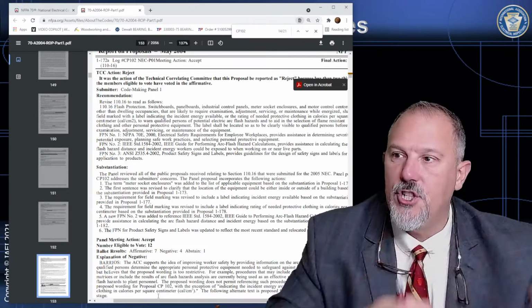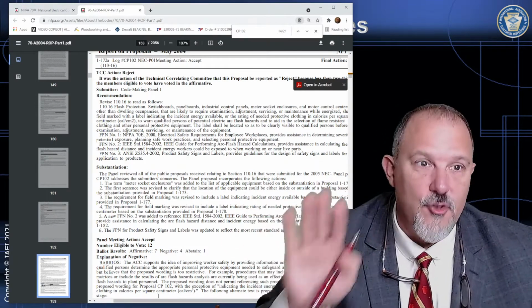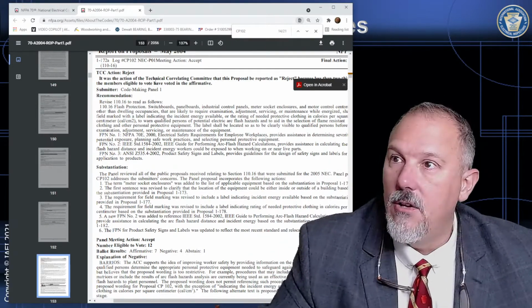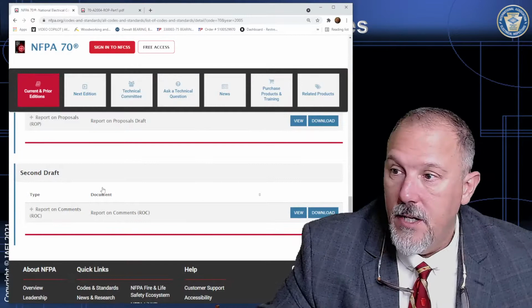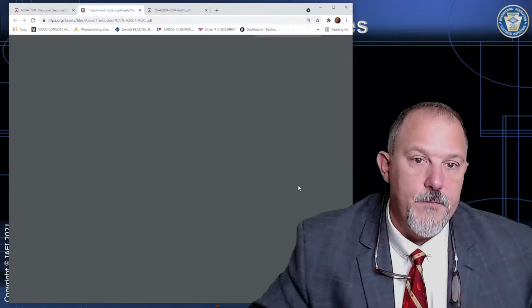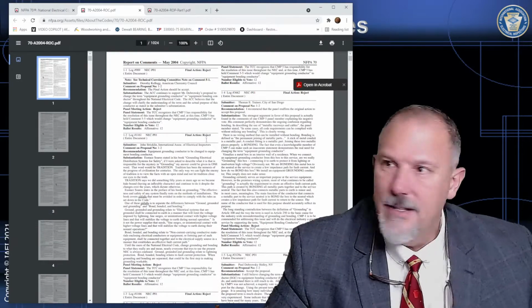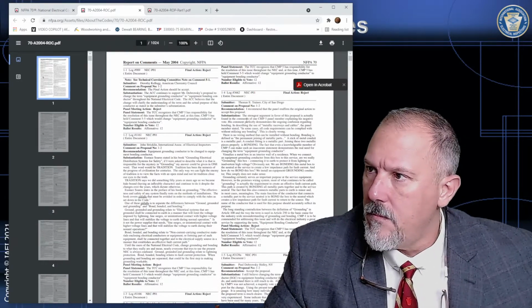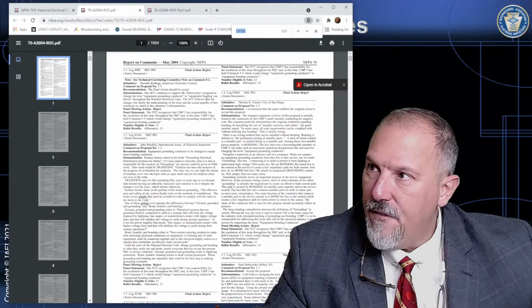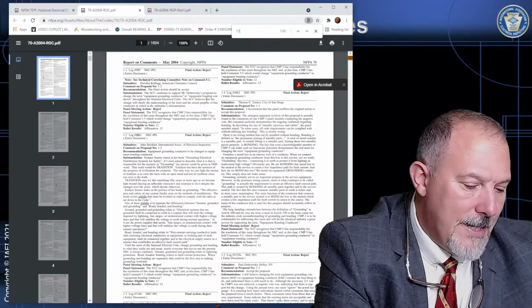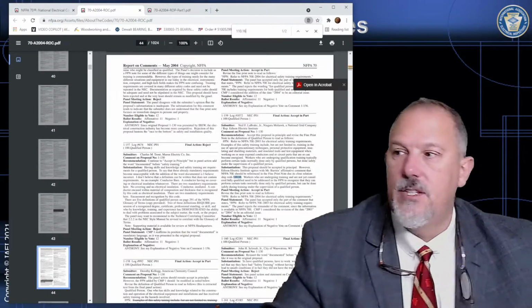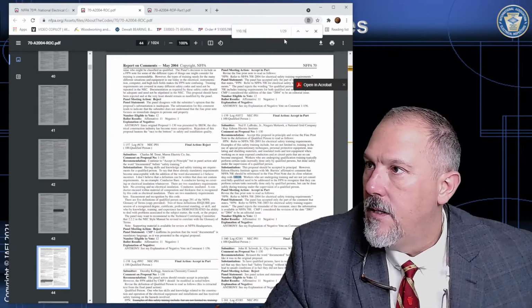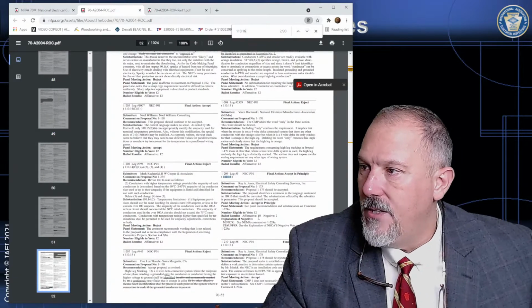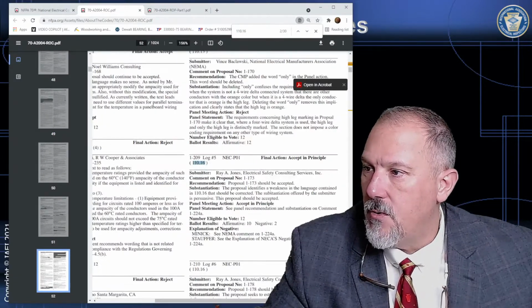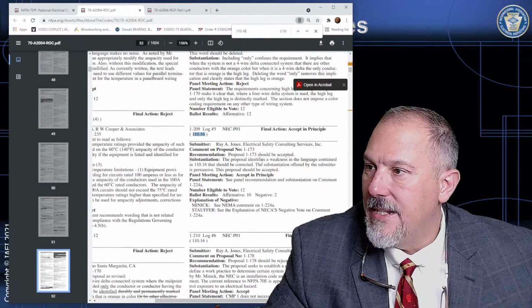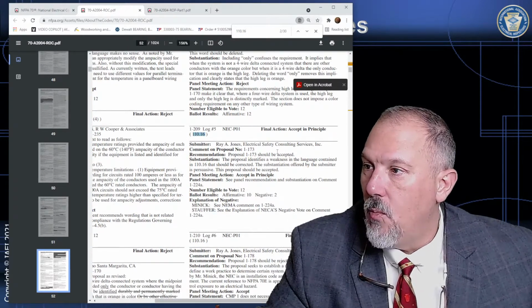The panel kept pushing back on that. This is the first draft. This is the proposals. Let's take a look and see what happened in the comments phase. So there's a report on comments. We're going to hit view. I love this stuff. Don't you love it? Come on, you've got to love it. And we're going to do what again? We're going to do a Control F for find, and we're going to search 110.16 because it's no longer a dash. And there it is, 110.16, accept in principle. The proposal 1-173 should be accepted. And that was accept in principle, 1-173.